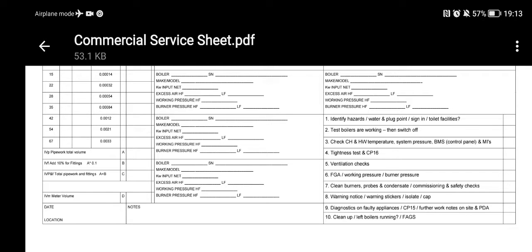Stage four: tightness test and CP16. I turn my boilers off as soon as possible — whilst they're off, you reduce the risk of scalding yourself or getting burnt touching burners or probes. In the time the boilers are cooling — it could be an hour — you can carry out other checks such as a tightness test and CP16 paperwork: volume calculations, pipe size, meter size, and fill in the details on this sheet.